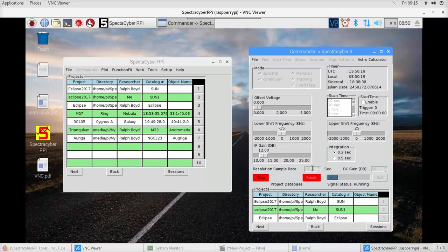So now this also has an effect upon how quickly we can take data over this time period. These things will interact. Your sample rate and your timer, when used in a frequency mode, will all interact. The software will attempt its best guess to tell you that you need to make some changes in order to acquire this data.